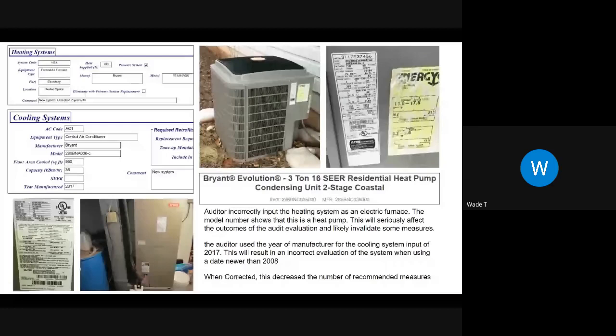Yeah, just exactly what you said is spot on. The heat pump is going to be doing the bulk of the heating, probably somewhere around 80 to 90% of the heating performed by the heat pump, and the heat strips are simply supplemental. If they're set up right, they'll be doing very little of the heating or contributing to the heating. And if you get into a situation where you're questioning that, and you're feeling like this particular heater's heat strips are on all the time, if you've got some way to show that, just put it in your notes. If you're making a decision a certain way, make sure you're commenting and documenting why you're making that decision. That kind of stuff will help clear up any questions that anybody reviewing this file might have.